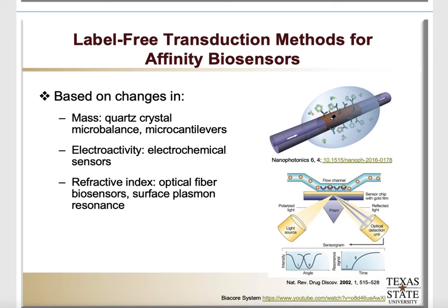We can modify the surface of that optical fiber to incorporate biorecognition molecules. And as more and more material deposits onto that surface due to specific binding, you can change the refractive index, and that's going to have changes on the light that goes to the other side, which you can then detect utilizing a photodetector.